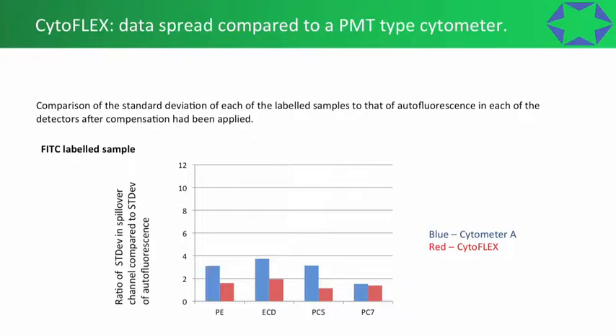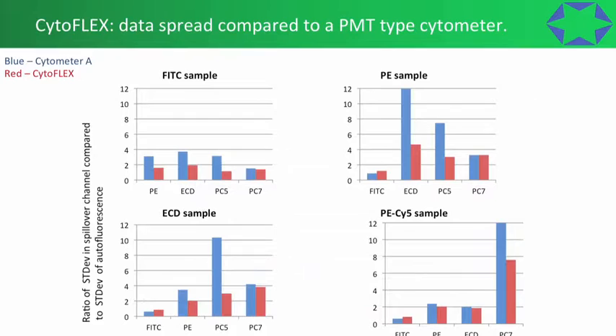Now we have the CytoFLEX in red, with lower values being better — less data spread. There is less data spread from the FITC sample into neighboring channels on the CytoFLEX. Looking at other stained samples: for the PE sample we've got the most data spread into neighboring channels, but in each case there is less data spread in the CytoFLEX compared to the other cytometer. For the ECD sample, there's quite a large amount of data spread in cytometer A, but this is much lower with the CytoFLEX.